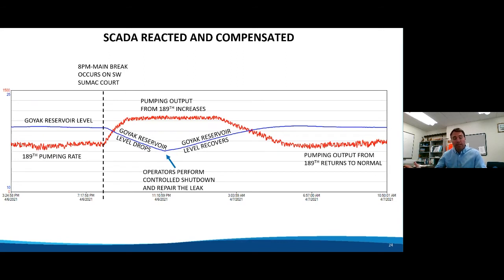Now our operators got out there. They shut down that leak. They used the valves that we have throughout the system to isolate that, and they were able to stop that hemorrhaging. We got a tourniquet on that, and you can see when that happened because that's when the tank level starts to recover. Once that tank level recovered to a certain amount, Scada sensed that as well, was able to ramp down that pumping rate, and all was back to normal. So pretty cool example of automation and compensation.